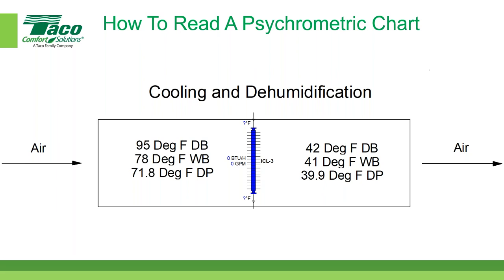But we're going to start off with some fairly common numbers in our industry. I'll highlight this, making sure I'm using red again. So we have air, let's say this is outside air, OA, and the temperature is 95 degrees Fahrenheit dry bulb, 78 degrees Fahrenheit wet bulb. I looked up the dew point temperature on my psychrometric chart prior to this presentation, and it came out to be 71.8 degrees. Now I'm going to cool that air down to 42 degrees Fahrenheit dry bulb, and about 41 degrees Fahrenheit wet bulb.